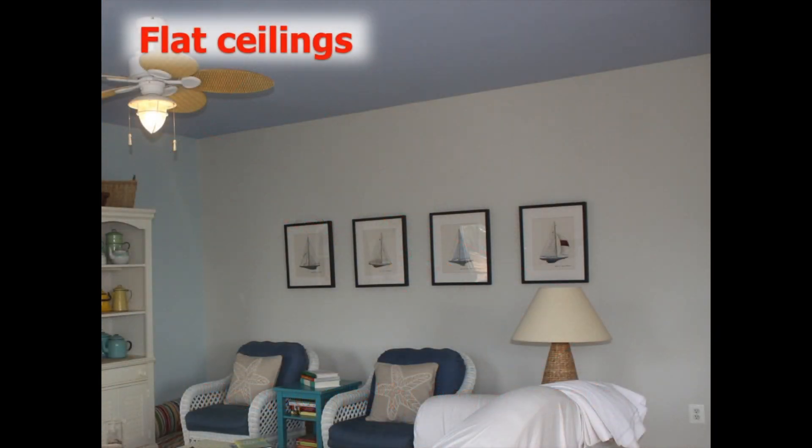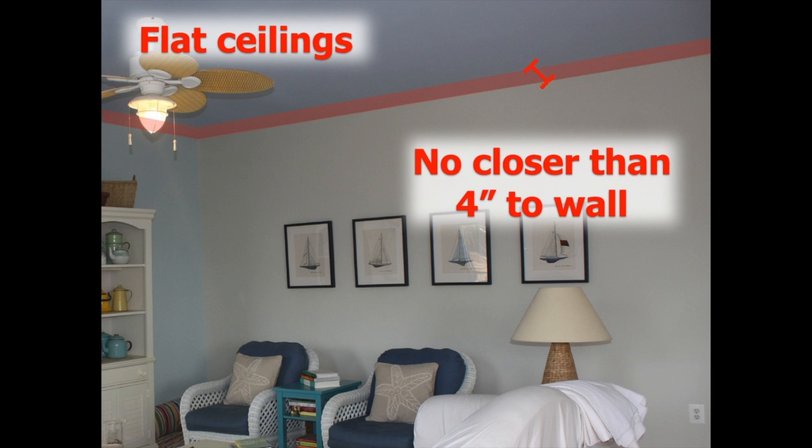For flat ceilings it's a little different. You just want to stay out of the corners. You can't be closer than four inches to the walls on flat ceilings. Otherwise you can install the alarms anywhere else along those flat ceilings.